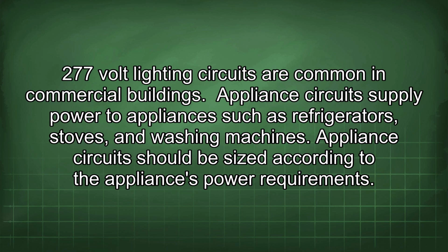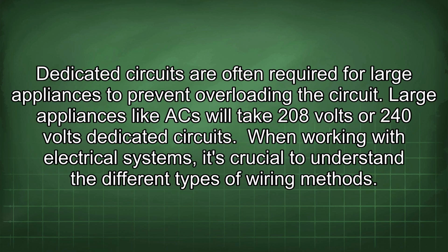Appliance circuits supply power to appliances such as refrigerators, stoves, and washing machines. Appliance circuits should be sized according to the appliance's power requirements. Dedicated circuits are often required for large appliances to prevent overloading the circuit. Large appliances like AC will take 208-volt or 240-volt dedicated circuits.